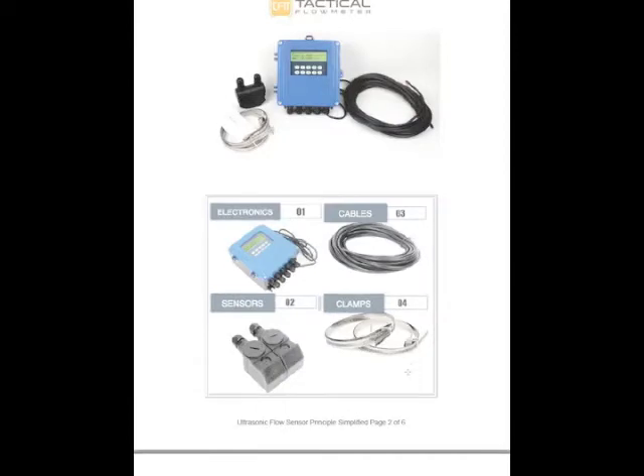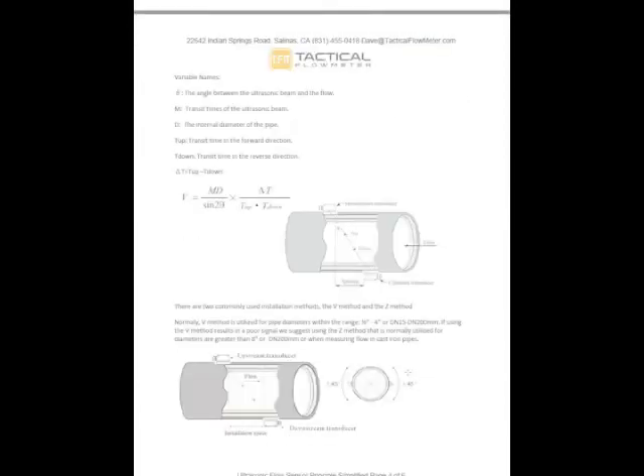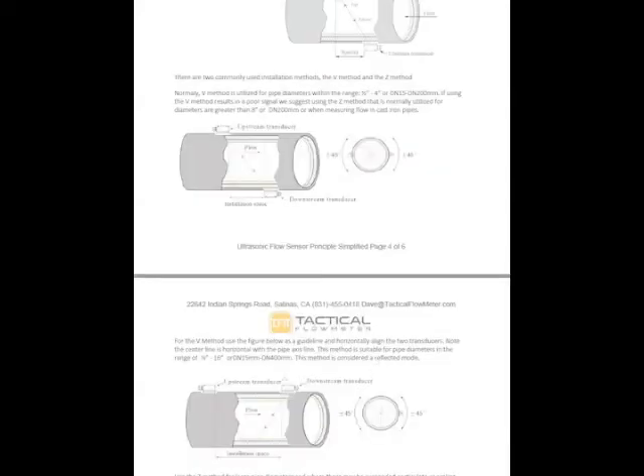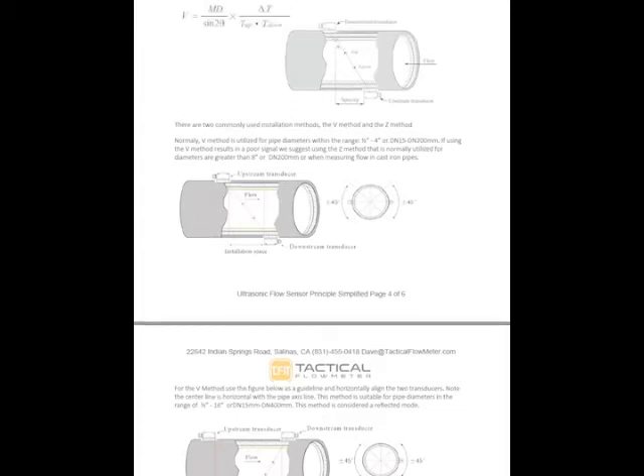The downside of these is that if you're not wonderfully careful how you place the transducers, because you're placing these on your pipes, and you don't follow the instructions precisely and use a micrometer to get the distance between these 2 faces, that's what they're referred to, and you don't clean the contact between these sensors, it's not a wonderful thing. The signal is weak, but the distance is critical, because that's how we're determining the D, the transit time within the D. So we're looking at the velocity within the D.